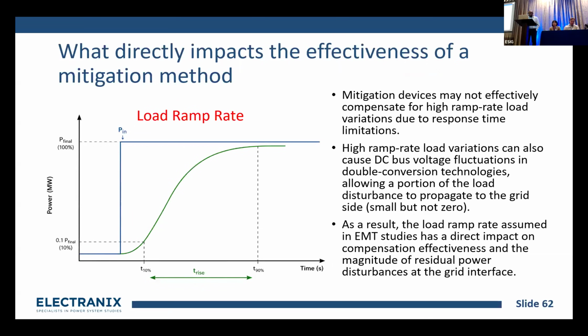So this is an important one. What really affects the efficiency of a mitigation method is the load ramp rate. You can ramp a load in a step way, meaning an instantaneous step in power, or you can do it with a second order function, like the picture on my screen. What is realistic? Because you can make this load ramp with different ramp rates, in such a way that you will have some residual power left at the grid side, which can pass or which can fail.